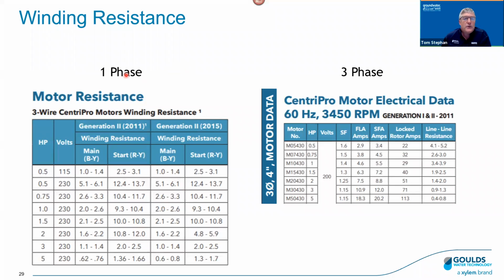Let's take a quick look here. What is the difference between the winding resistance of a single phase motor versus 3-phase? With a single phase motor, we can see the range, and we use this for an example, a half 230 again. You've got 3 wires, right? The black and yellow is 5.1 to 6.1. The red and yellow, otherwise called start, is 12.4 to 13.7. So that's where you would look those values up.